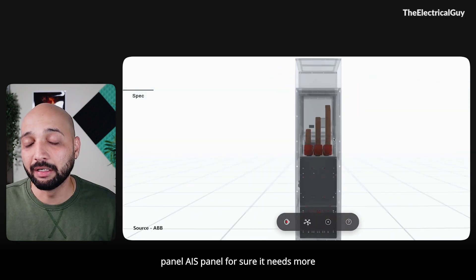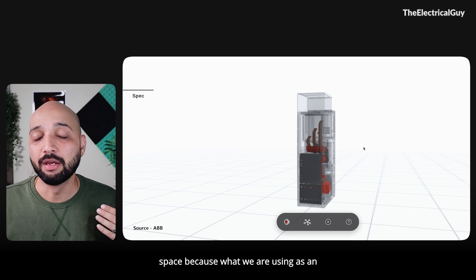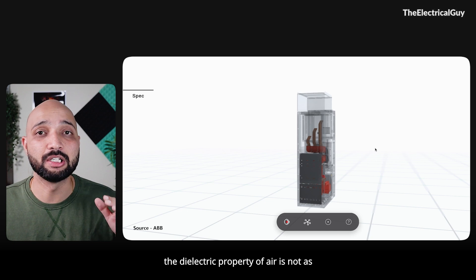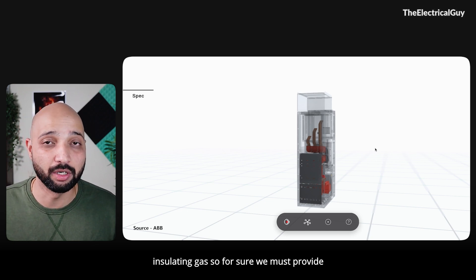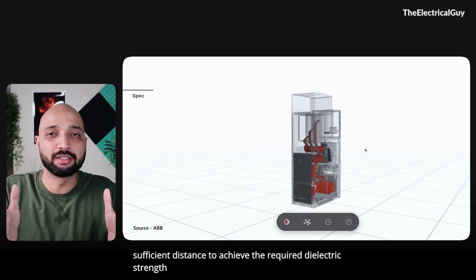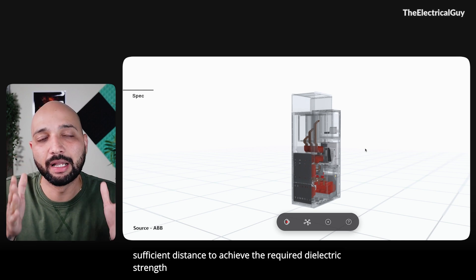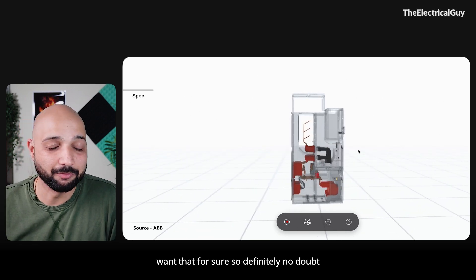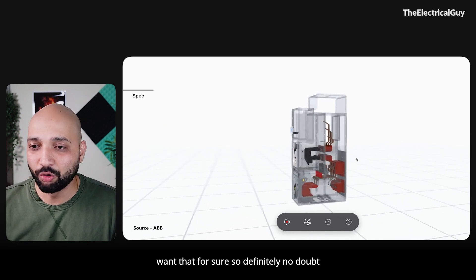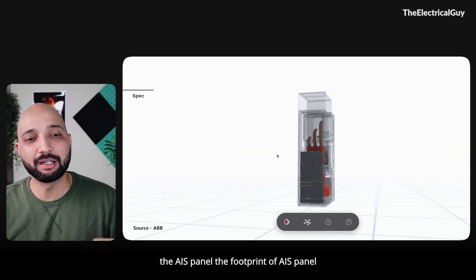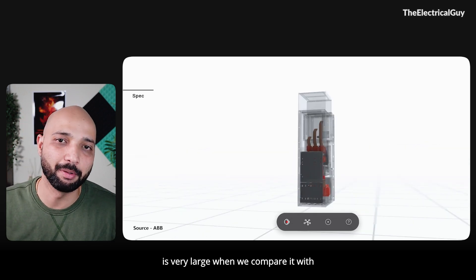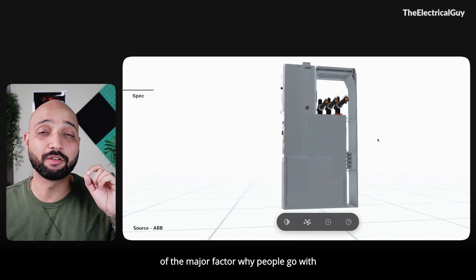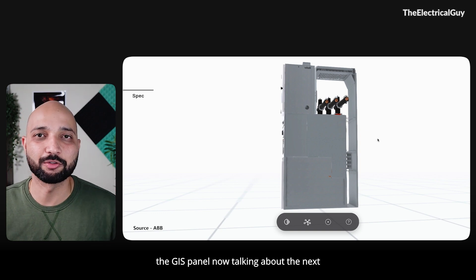AIS panels need more space because the insulating medium is air, and the dielectric property of air is not as good as SF6 or any other insulating gas. We must provide sufficient distance to achieve the required dielectric strength. So the footprint of an AIS panel is very large compared to an equivalent GIS panel — this is one of the major factors why people go with GIS panels.